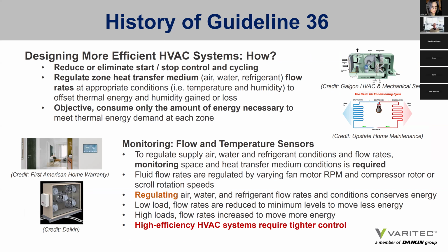So how do we design a more efficient HVAC system? Reduce or eliminate start-stop control and cycling. Regulate zone heat transfer medium flow, like blood flow in the human body, at appropriate conditions to offset thermal energy and humidity gained or lost. The objective then is to consume only the amount of energy necessary to do that. Well, in order to control heat transfer, you have to monitor. You have to monitor flow and temperature.